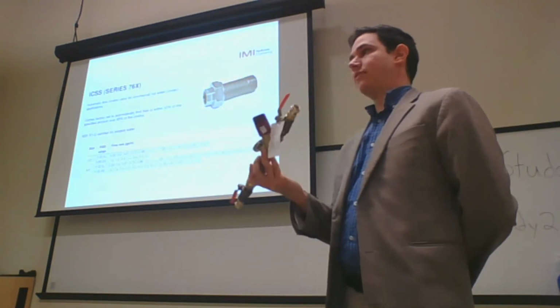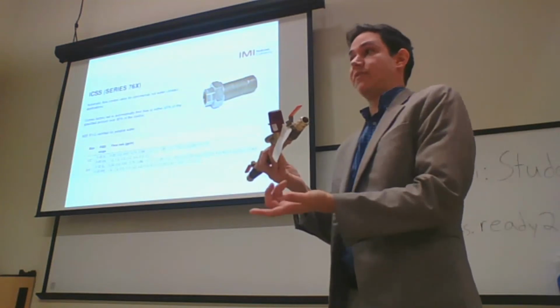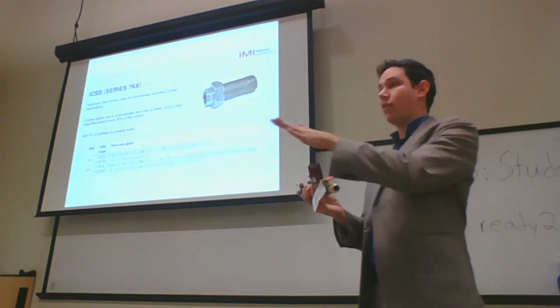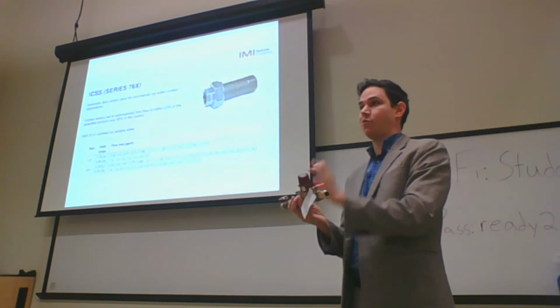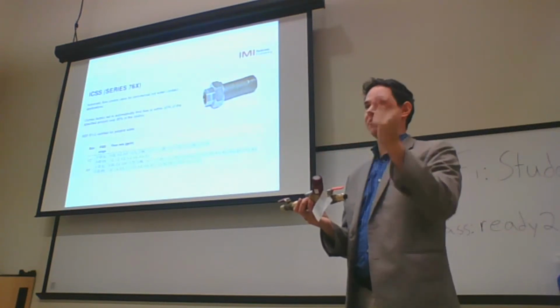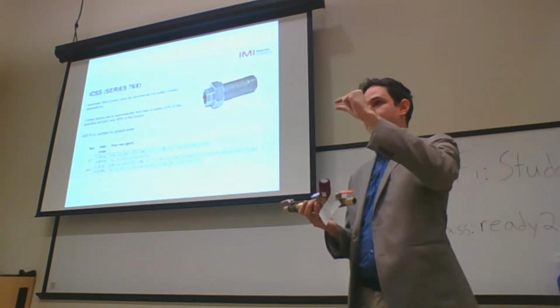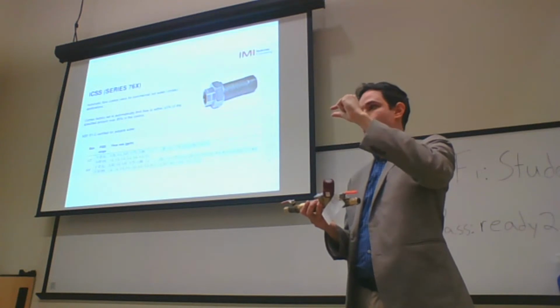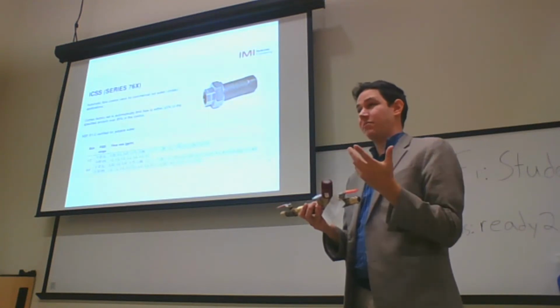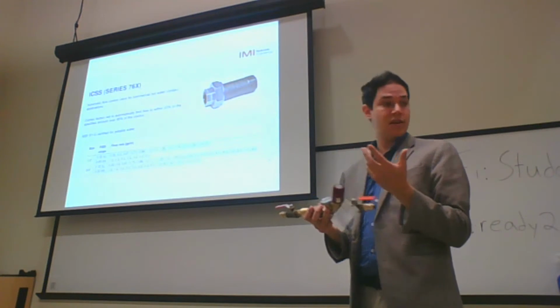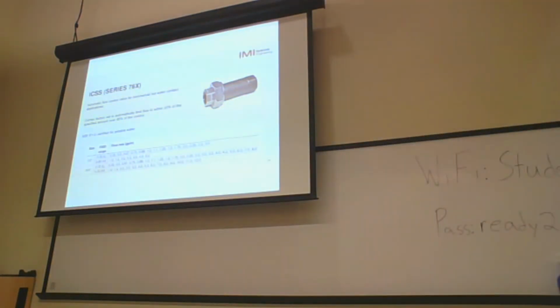Right. So if you measure the delta P and you know the CV, you have the flow rate for the report. But the difference is this valve is variable. So right now, when you're taking the measurement, it could be at one CV. Five minutes later, at a different temperature, it would be a different CV because this valve is always operating. It is kind of the same as an automatic balancing valve. An automatic balancing valve, you cannot measure.